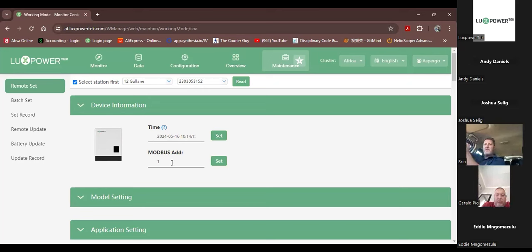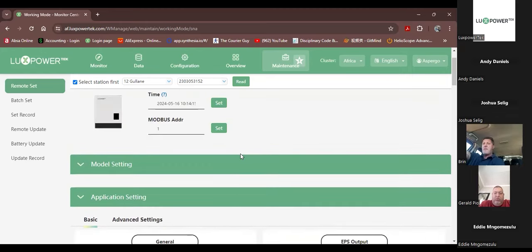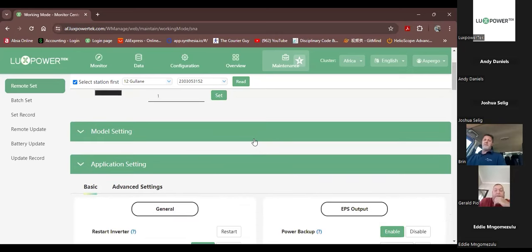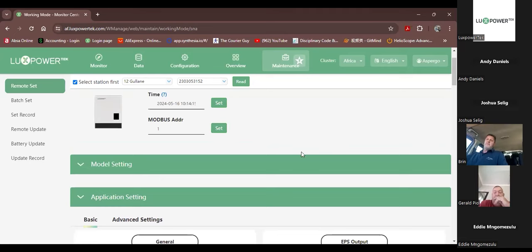All right, the Modbus address, please don't change this. A Modbus protocol is what we use when we communicate between multiple inverters in parallel, and we're using protocol 1 for that. Please don't change that, because it will change how the machines communicate with each other. Modbus is basically just a push communication to the receiver, and also push for receiving data back. And we use this Modbus protocol here, so please don't change any of that.